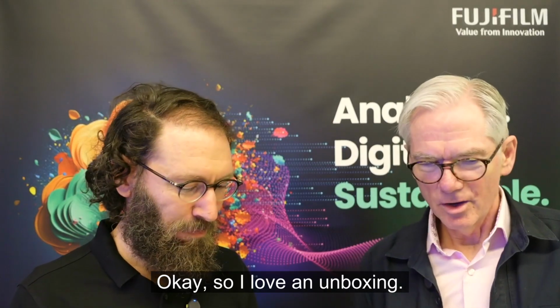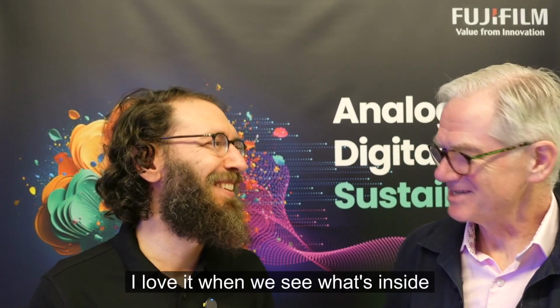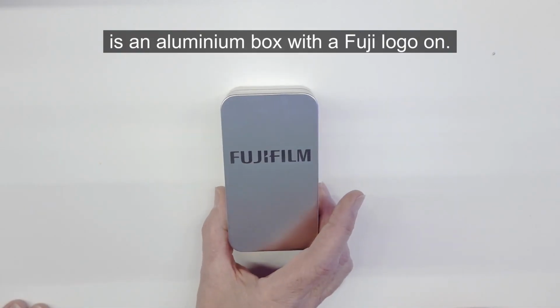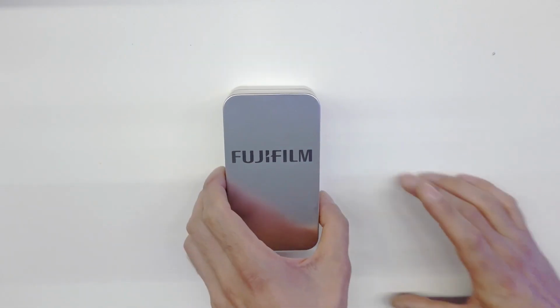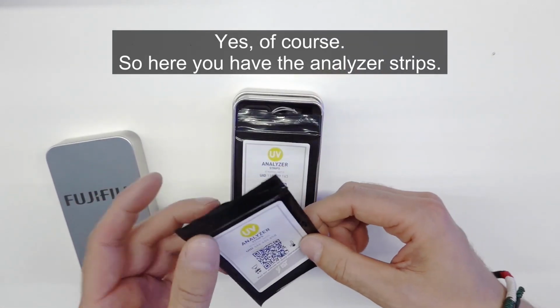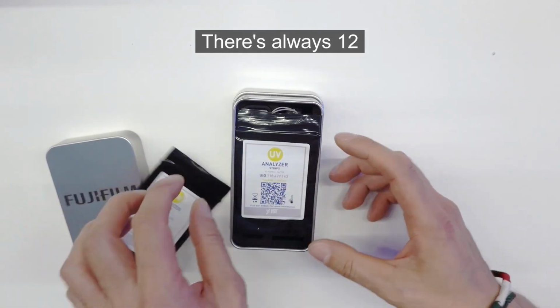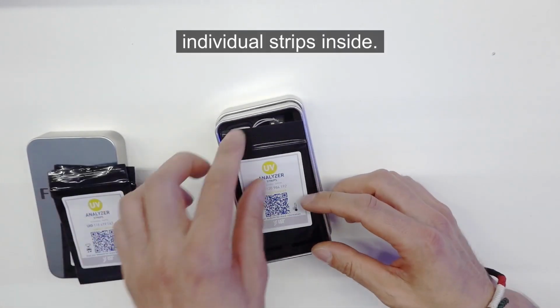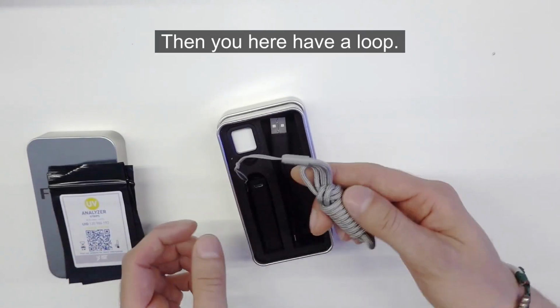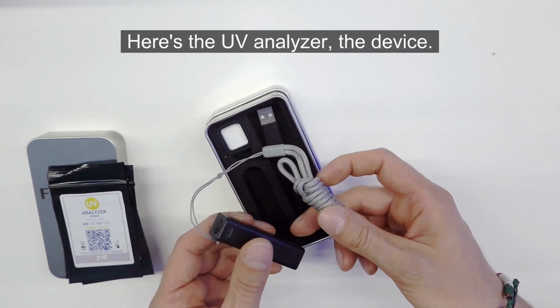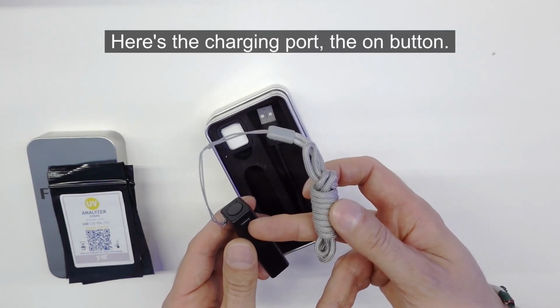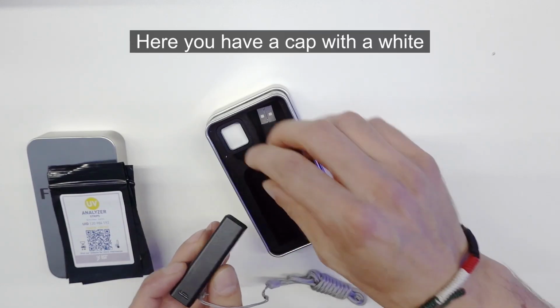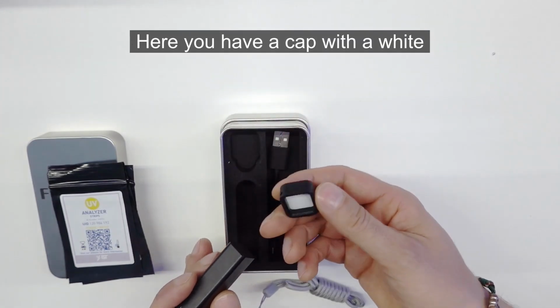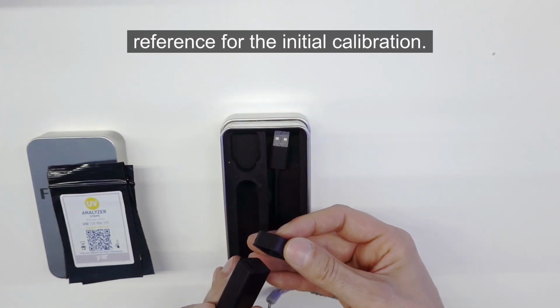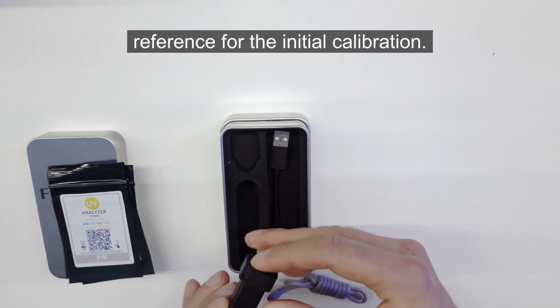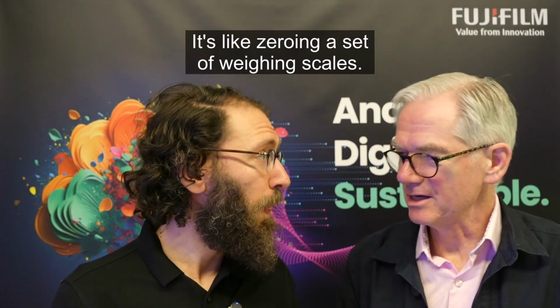Okay, so I love an unboxing. I love it when we see what's inside the box, and all we've got at the moment is an aluminium box with a Fuji logo on. So could you take us through what's inside? Yes, of course. So here you have the analyzer strips. There's always 12 individual strips inside. Then you here have a loop. Here's the UV analyzer, the device. Here's the charging port, the on button, and here you have a cap with a white reference for the calibration, the initial calibration. So it's like zeroing a set of weighing scales.